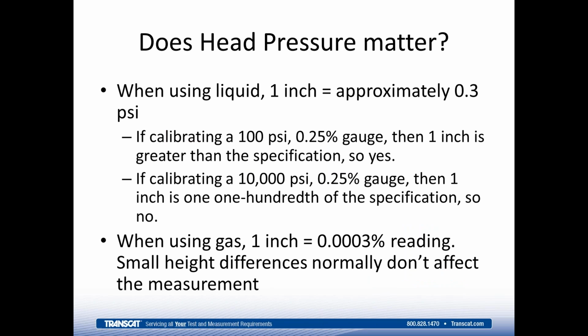So, does the head pressure matter? How big of a change are we really talking about? When you're using liquid, 1 inch of height difference is approximately 0.3 psi. So if you're calibrating, say, a 100 psi gauge, and that gauge has a specification of 0.25% of full scale, that means it would have a specification of plus or minus 0.25 psi. In that case, if we're using liquid as that media, and our two gauges had a different height of about 1 inch, then even if both gauges were perfectly accurate, our readings would differ by 0.3 psi. So if we don't account for that head pressure, we would be out of specification.